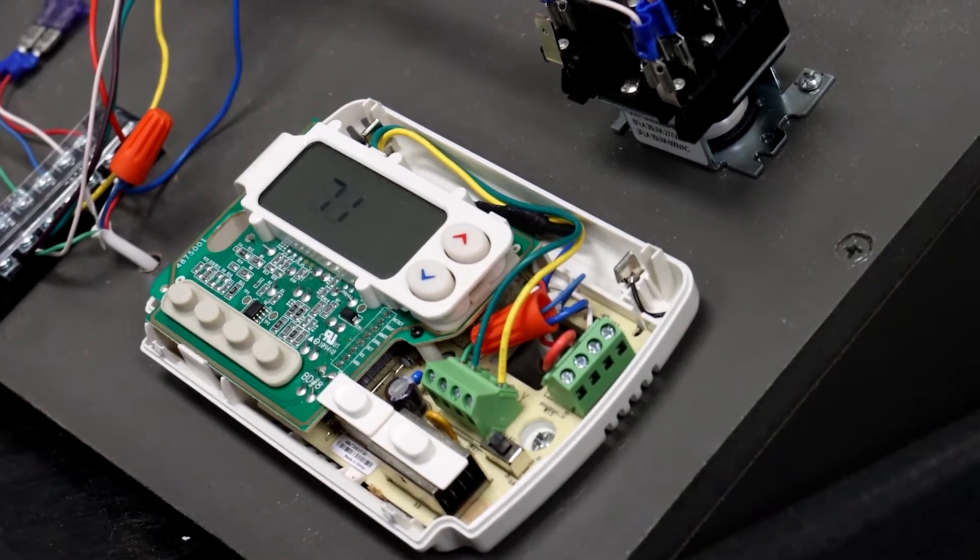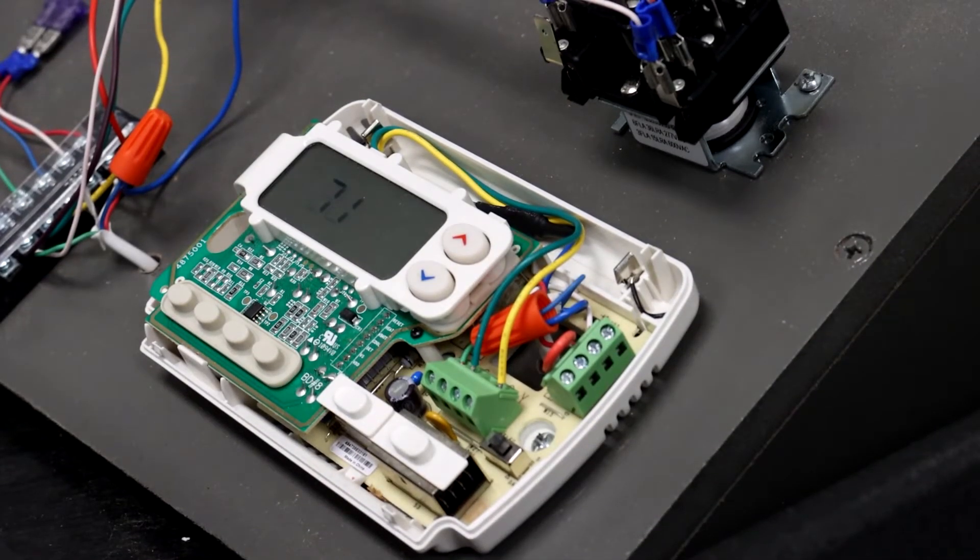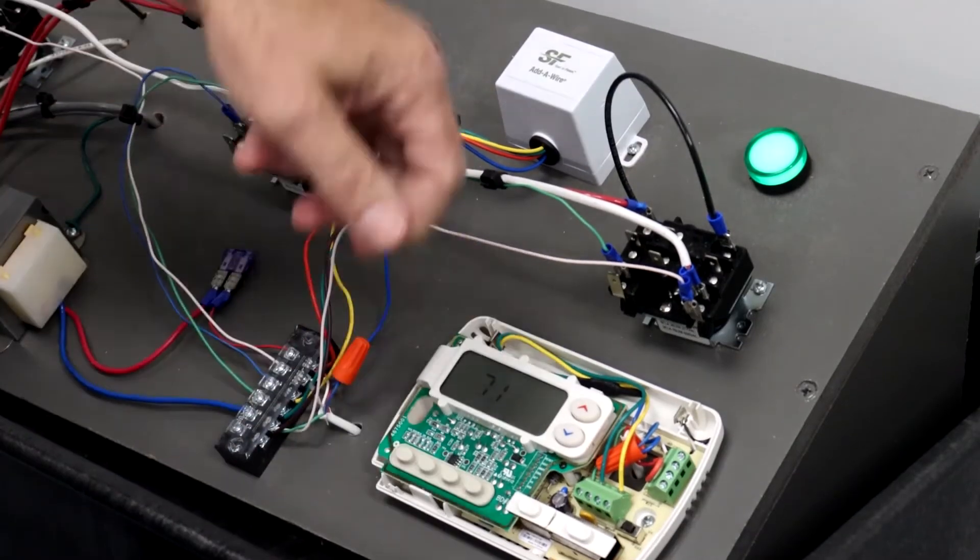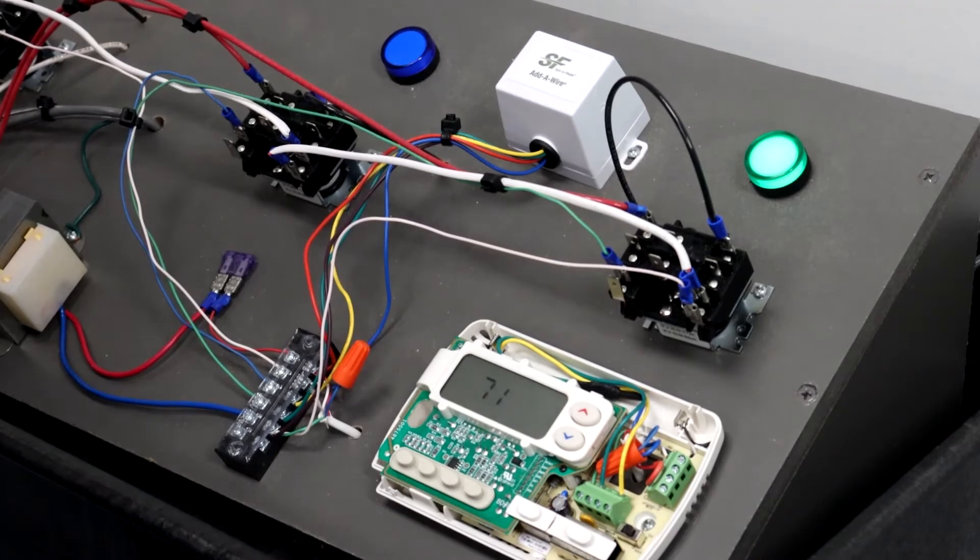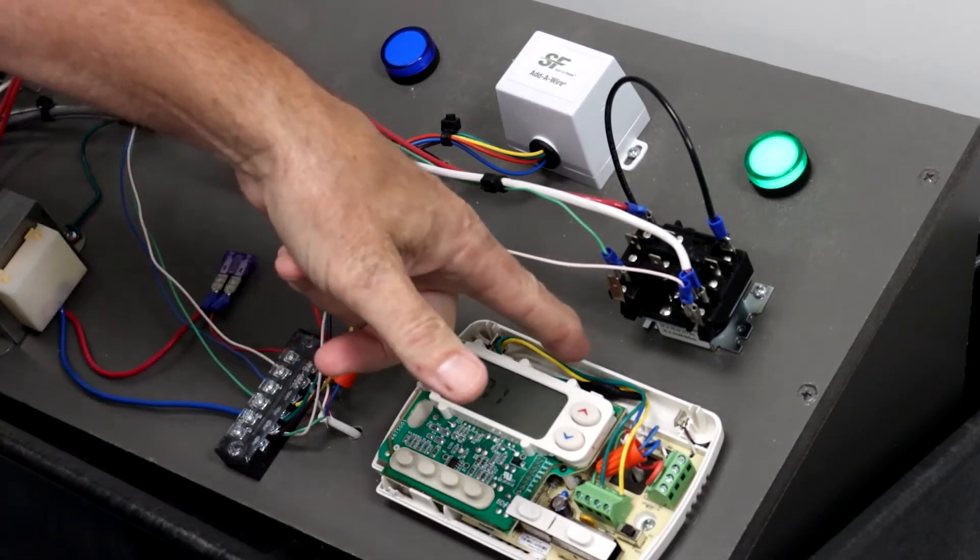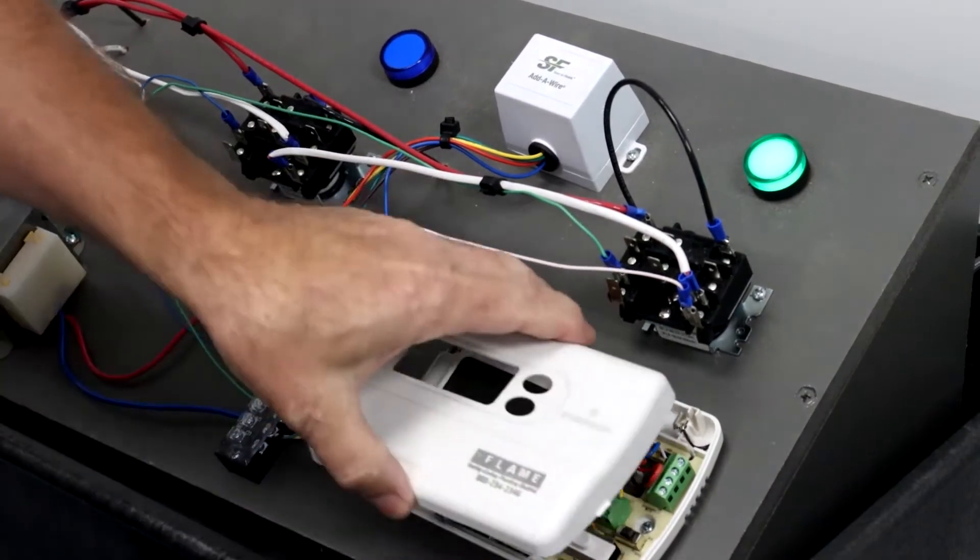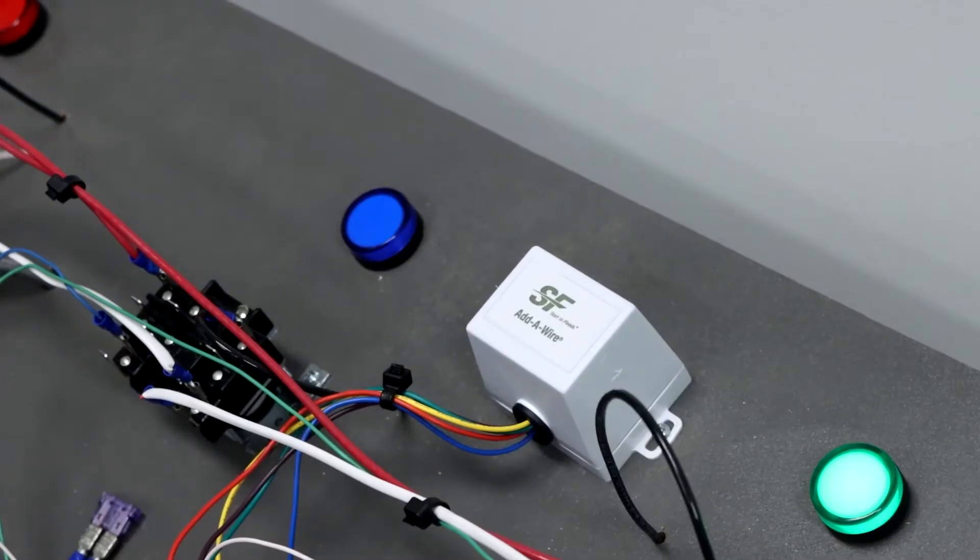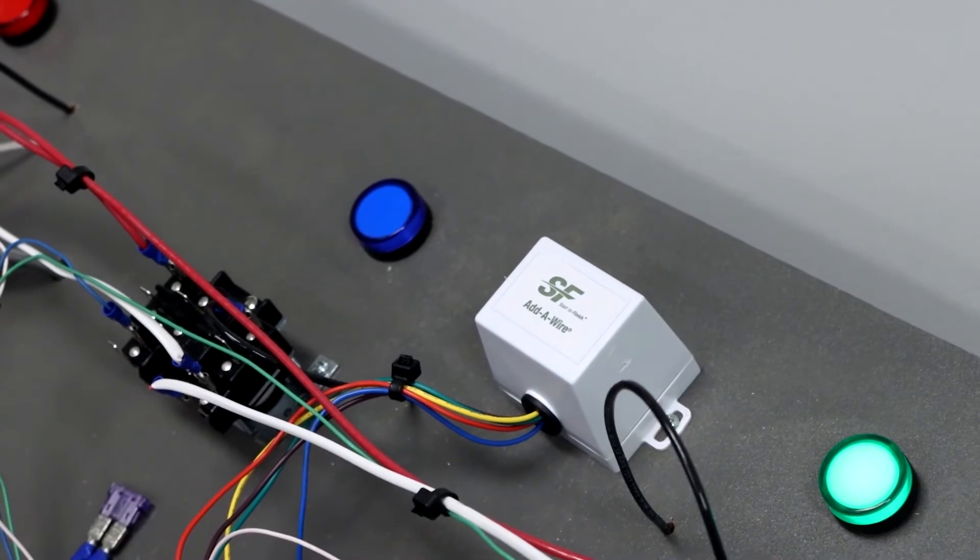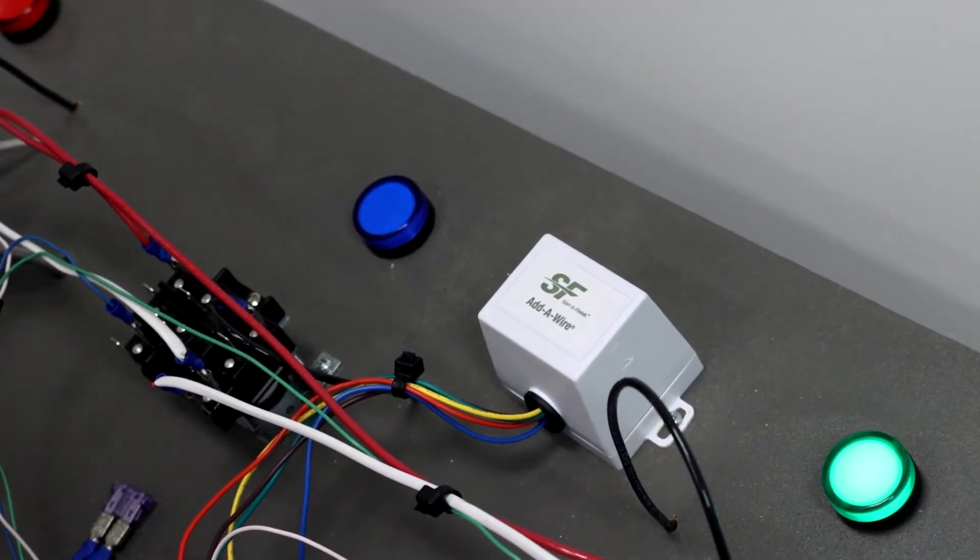Thermostats come with batteries so they can store the program. In this case with the Add-A-Wire, what it does is it takes four wires and makes it five wires, so that way we could get rid of the batteries and now the thermostats are hardwired. As long as there's power to the furnace, there's power to the thermostat, we don't need any batteries.